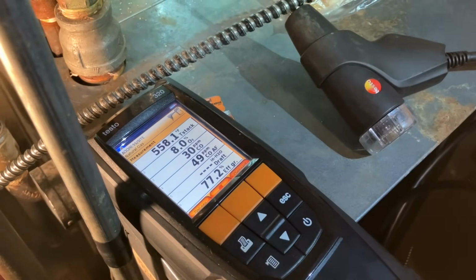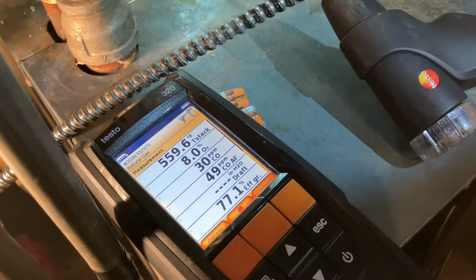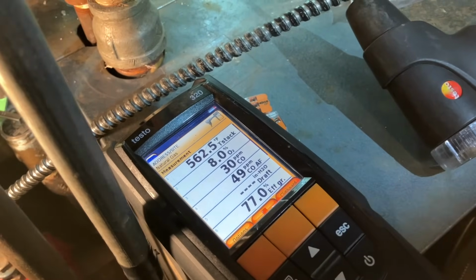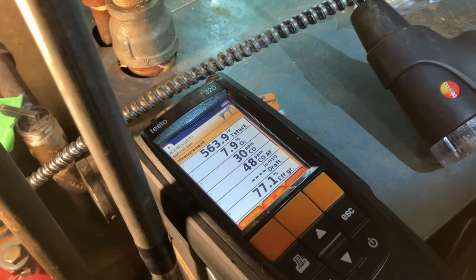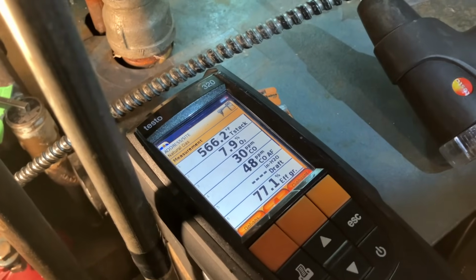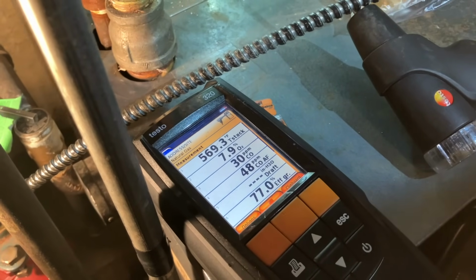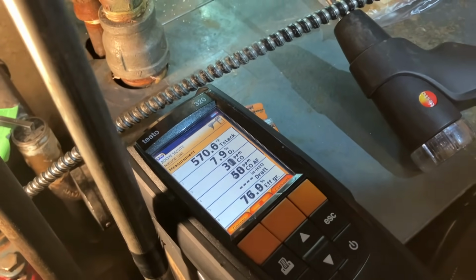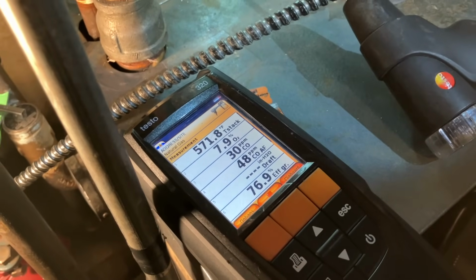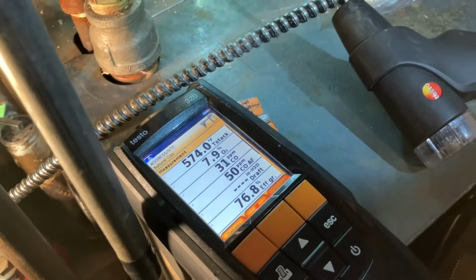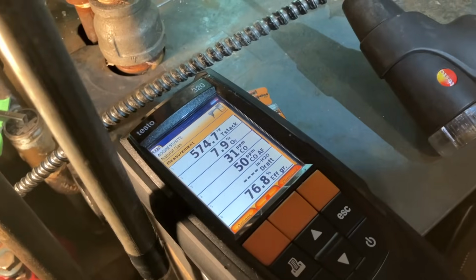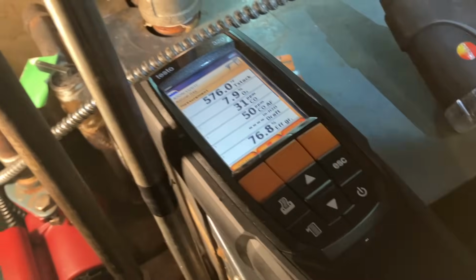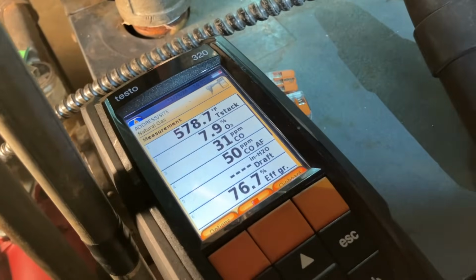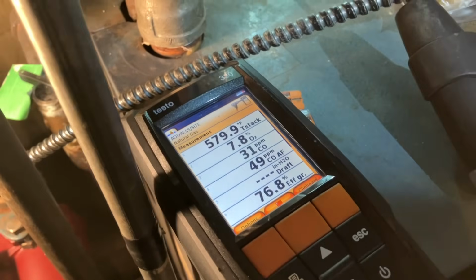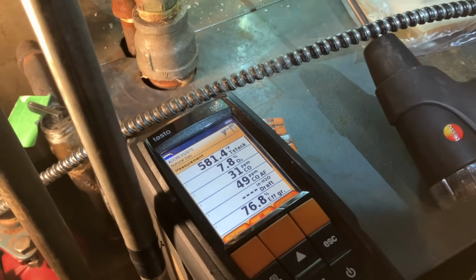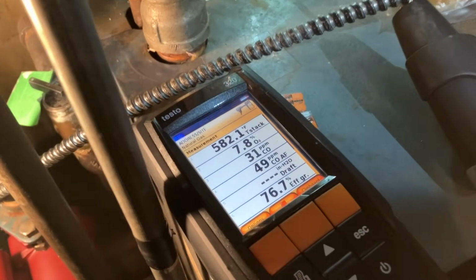So 77%, yeah, okay. To put it this way, the stack temperature leaving this boiler is 565 degrees right now. That shouldn't be that high, right? No. It should be in the high 3s, low 4s. This is more approaching oil territory. Oil-fired equipment. There's a lot of wasted heat there. And again, I'm not an oil expert by far. I don't know anything about oil. Let me just say that. But that stack temperature, I've been told, is oil territory. A boiler like this, a Weil-McLain CG something Gold gas-fired boiler, I was told you have in the high 5s.